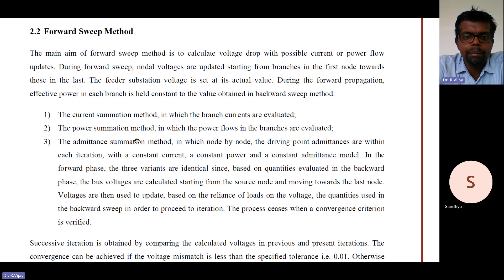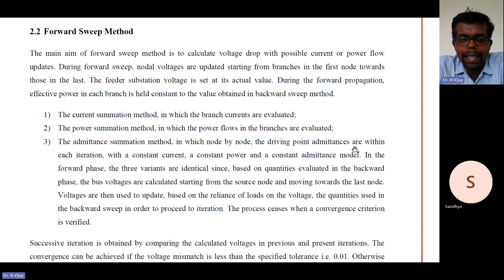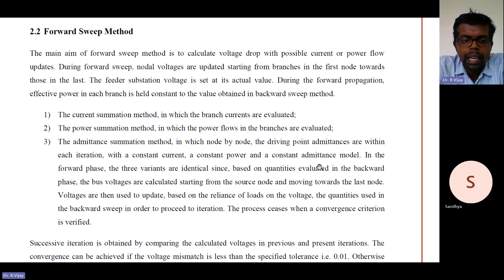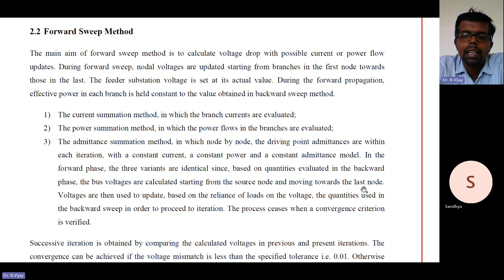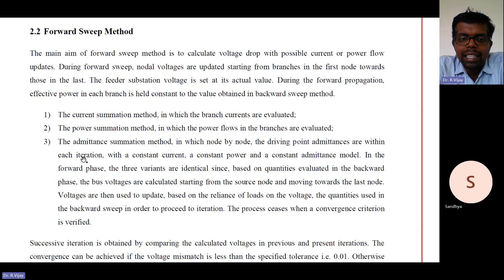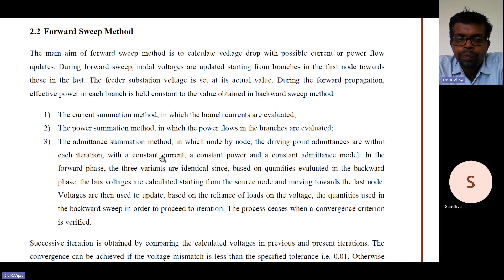The first variant is the current summation method, in which branch currents are evaluated. The second is the power summation method, in which power flows of each branch are evaluated. The third is the admittance summation method, in which node-by-node driving point admittances are computed within each iteration using the constant current, constant power, and constant admittance model. In the forward phase, all three variants are identical.